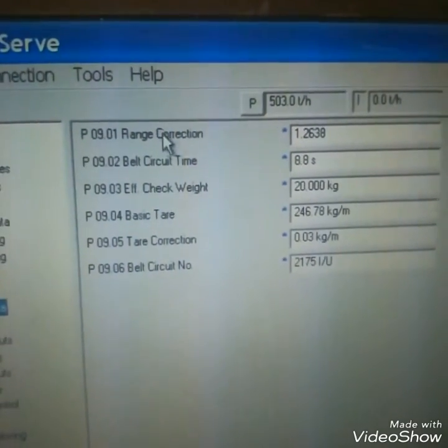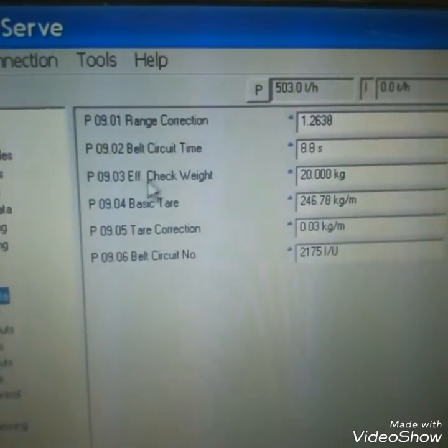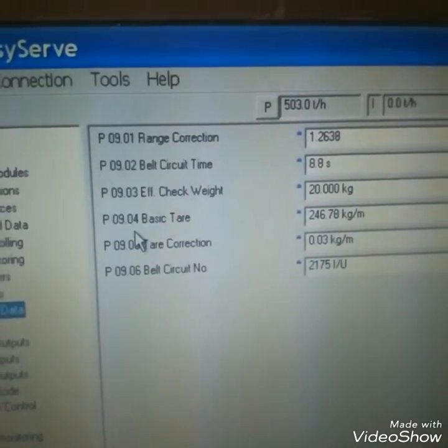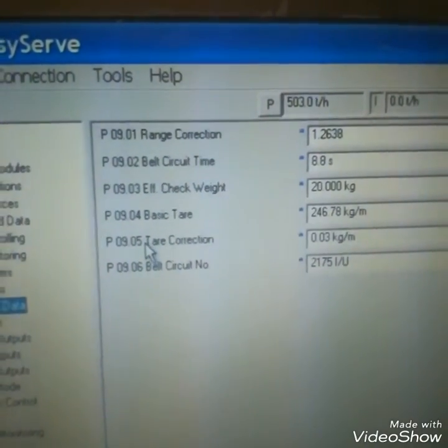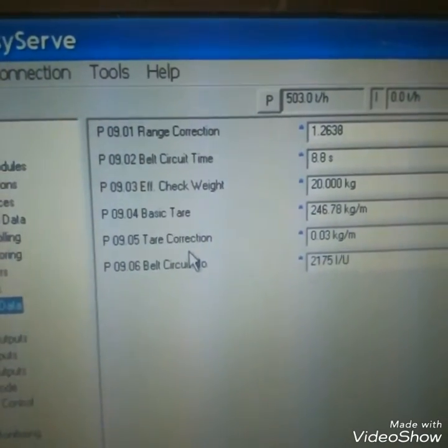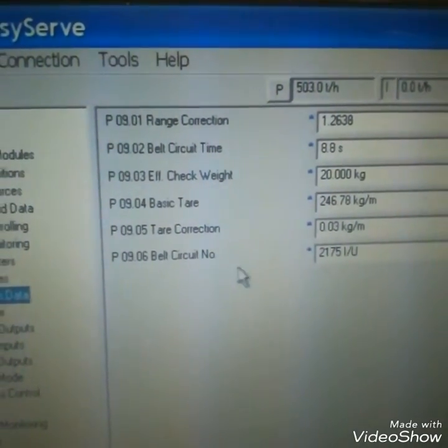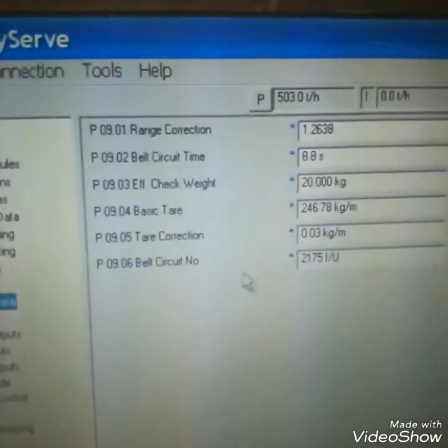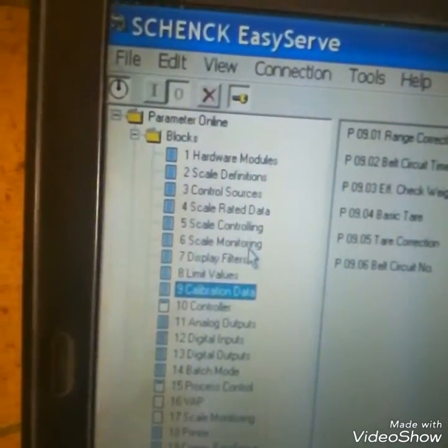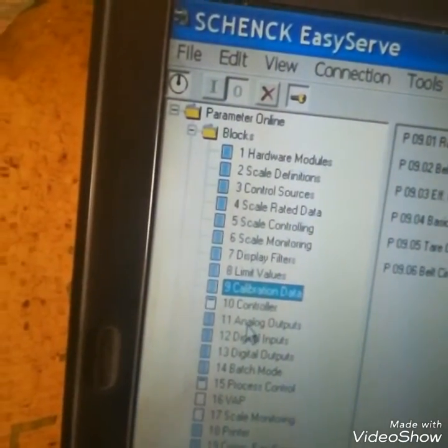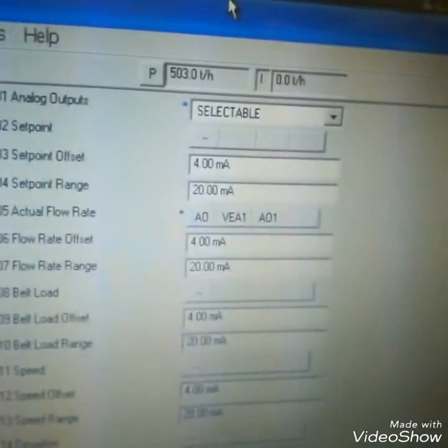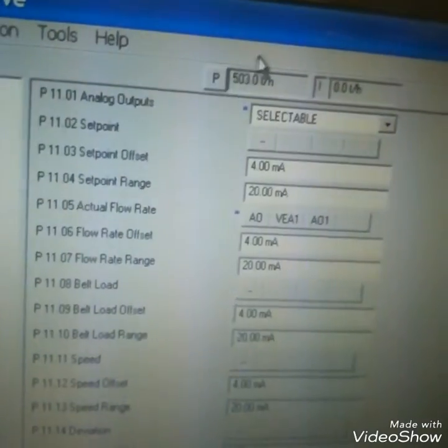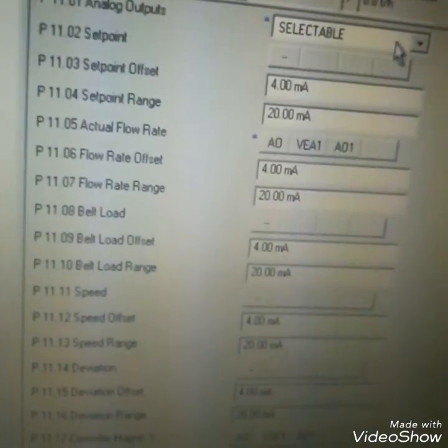This is calibration parameter. There is a range correction 9.1. If we change this range correction factor, calibration will be changed. There are parameters, what is basic tare, what is the belt circuit time, and what is the belt circuit number. So these are the calibration parameters. When we calibrate, span calibrate, we adjust this parameter 9.01 as per the calculation. So here I am showing you analog output block.